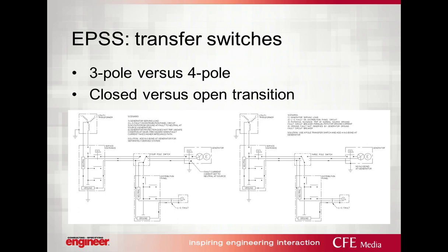Now, we have to talk about 3-pole versus 4-pole transfer switches. And that's going to be based on whether or not your system is separately derived. Simply put, what we're looking at here is the neutral current that's normally returning back to the source on the utility side, for example. If you have a 3-pole switch with a solid neutral, that neutral current is going to split and go in 2 different directions. It's going to try and go back to the emergency source and the normal source. And if there's any bonding on the emergency side between neutral and ground, then you're going to have return neutral current on your grounding system, which can cause nuisance trips of any of your ground fault breakers on your main distribution. The easiest way to solve that problem is with 4-pole switches and separately derived generators and normals.